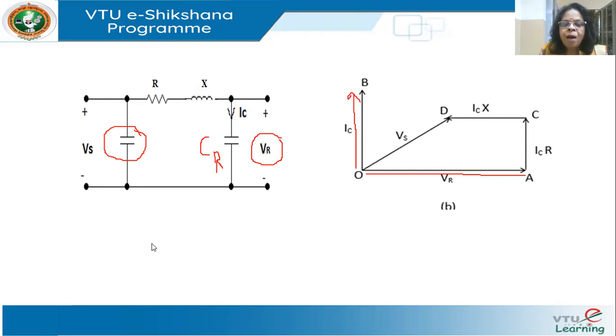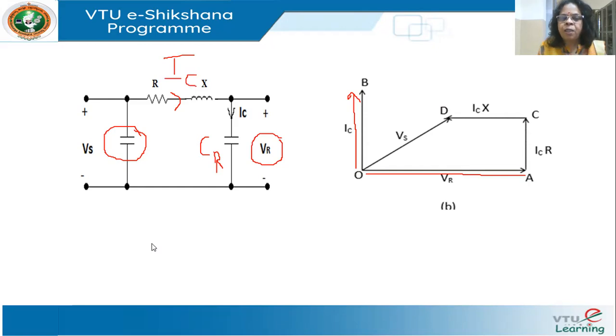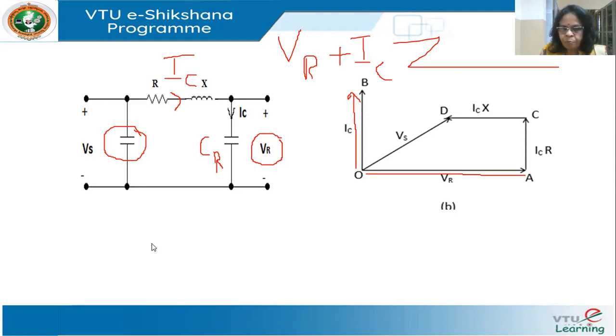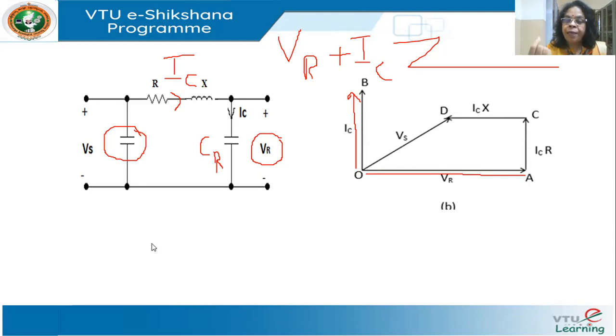The current flowing through the series impedance Rx will also be IC. The sending end voltage Vs will be Vr plus IC times Z, where Z is R plus jX. This drop has two components: the drop across the resistance and the drop across the inductive reactance. In a resistor, current and voltage are in phase, so the drop across R is in phase with IC. For an inductor, the voltage leads the current by 90 degrees, so the drop IC times X leads IC by 90 degrees.